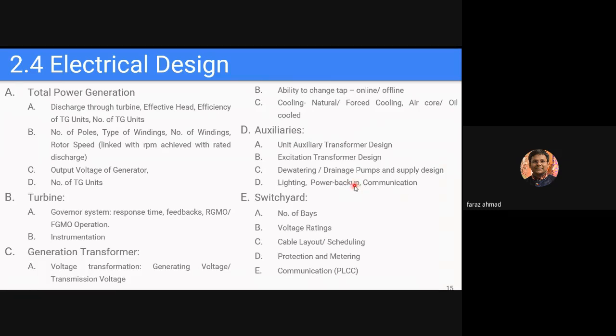After that, you have to design a switchyard. All these generating units transfer their power through a generating transformer into a switchyard, which is nothing but a switch with several protections. Since there's a lot of voltage involved, about 400 kilovolts, you cannot use a miniature circuit breaker for that. You need a very long switchyard, say 50 or 60 meters wide by a few hundred meters long, just to keep the voltage level harmless and so conductors don't interact with each other. You cannot have two conductors running very close to each other, as there will be discharge through the air gap, which is not desired.